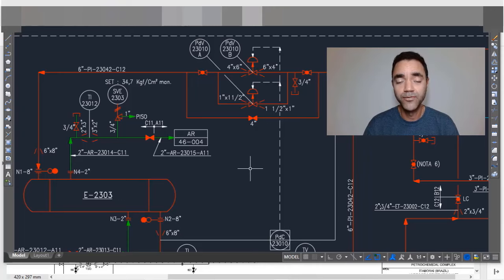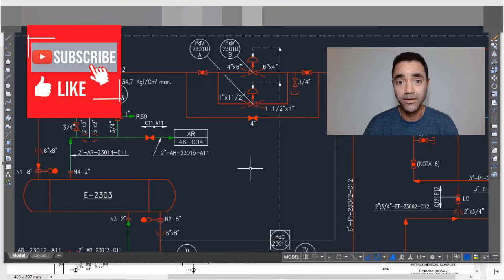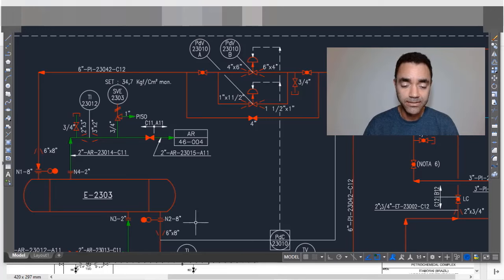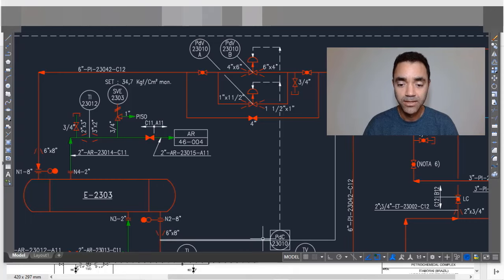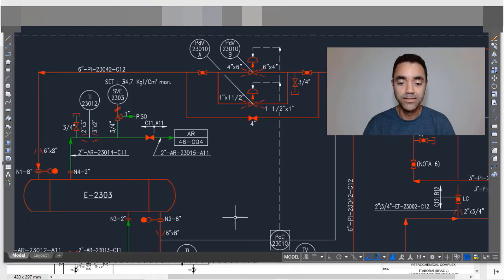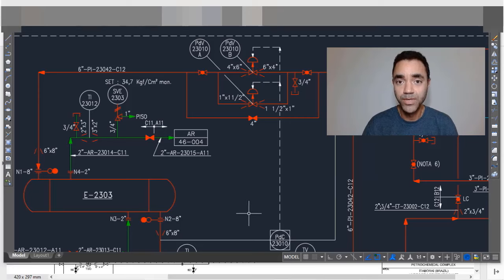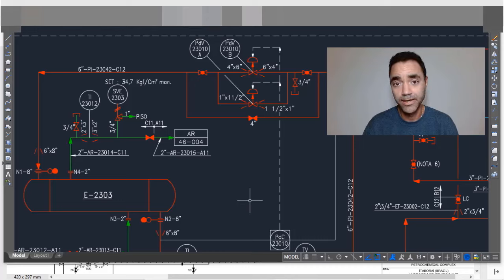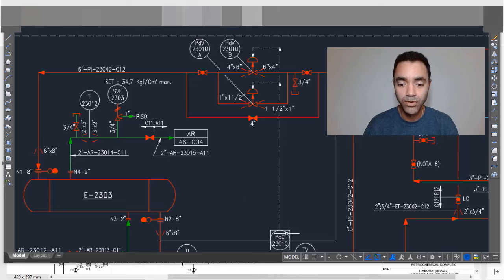Different companies have different ways to do the pipe instrumentation diagram. In the field, what we have is a tap with manual valves to isolate the PDC, and this PDC must be a transmitter — because if it's not a transmitter, it's not possible to send a signal to the PLC. But the way that the company draws its P&ID doesn't represent this kind of information in the drawing.